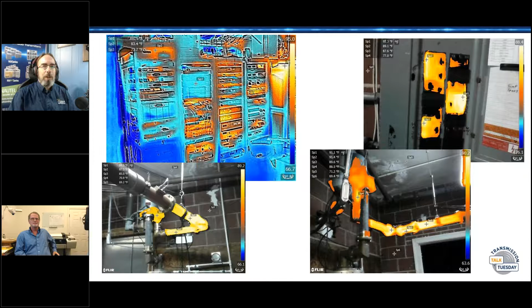As a matter of fact, the first service call I took for this particular client, which owns several stations, was an HT20 where the exciter had failed, they thought, blowing fuses. What I found out was that the little phase detector relay in there had failed. Popped the new one in and it's working.